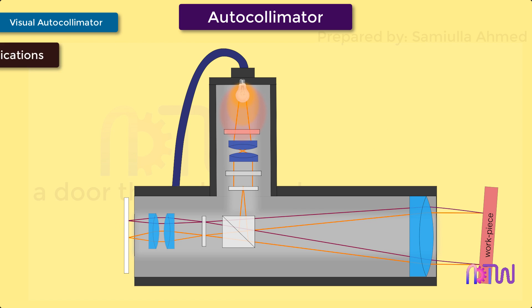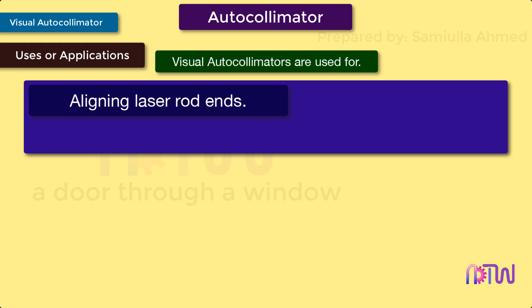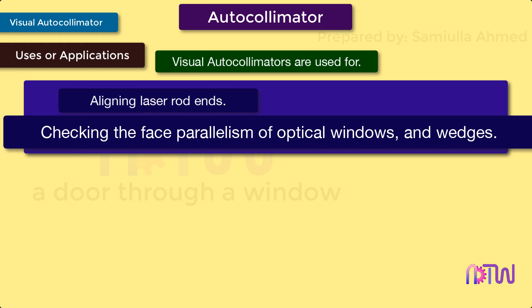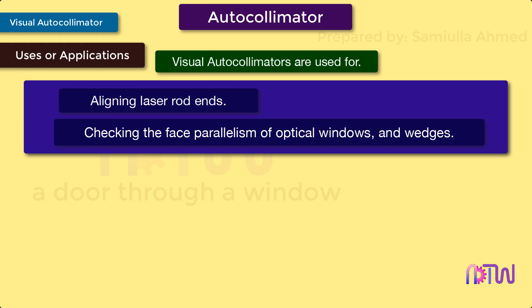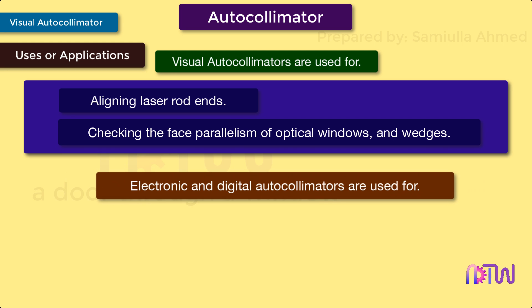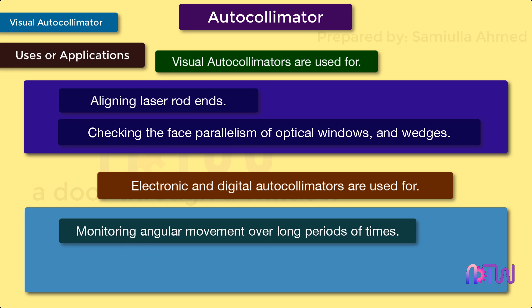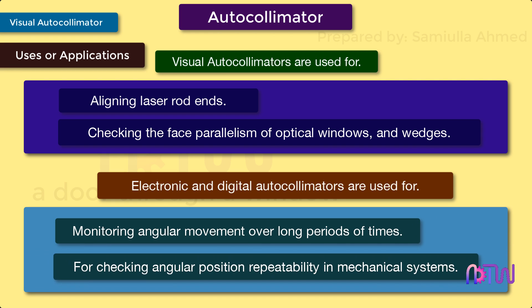Visual autocollimators are used for aligning laser rod ends and checking the face parallelism of optical windows and wedges. Electronic and digital autocollimators are used for monitoring angular movement over long periods of time and for checking angular position repeatability in mechanical systems.